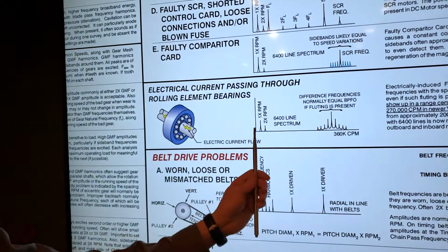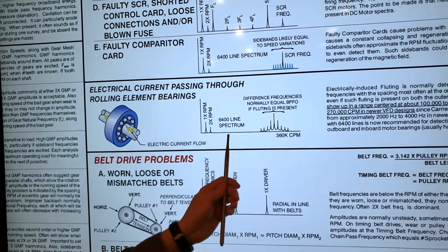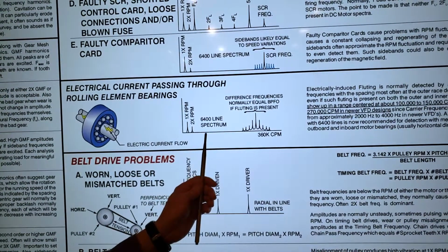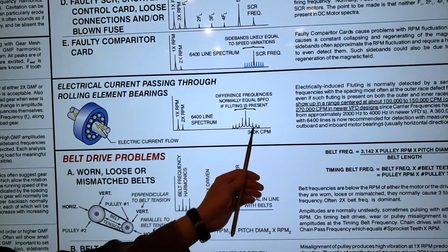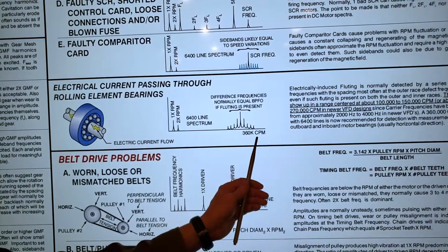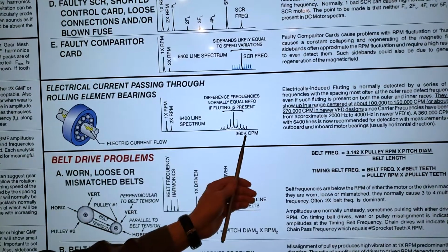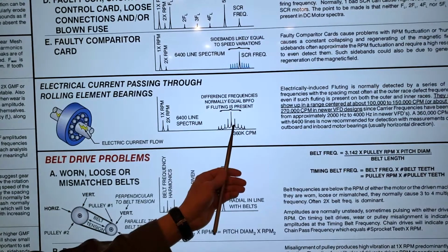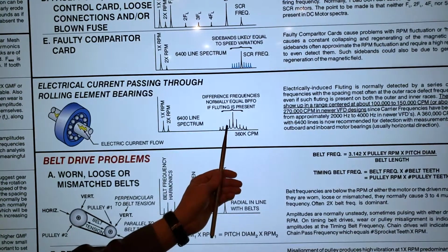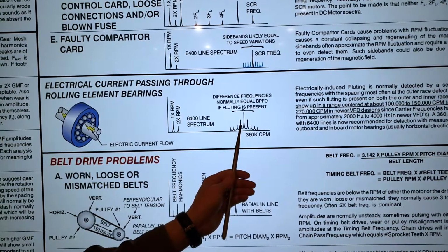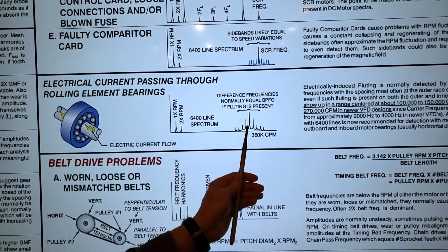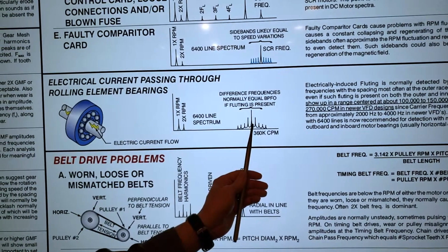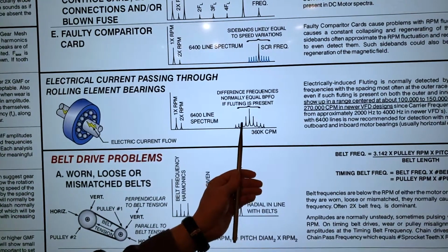If you look at a vibration spectrum, it's a very unique type of spectrum. You have your normal 1 times RPM and 2 times RPM, and then everything appears healthy until you get into the higher frequency regions, up as high as 6,000 hertz, 360,000 CPM. These sidebands are the key for which you're looking. Those sidebands are 95% of the time the outer race frequency for a particular bearing. Whether the fault is afflicting both the outer race and the inner race of the bearing, 95% of the time the sidebands are spaced at the outer race frequency.